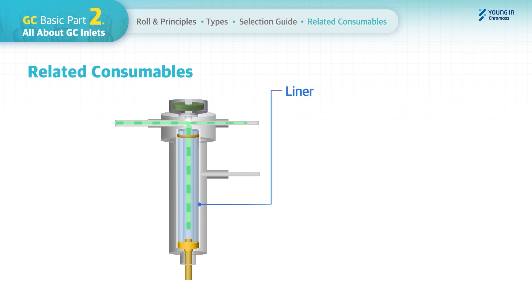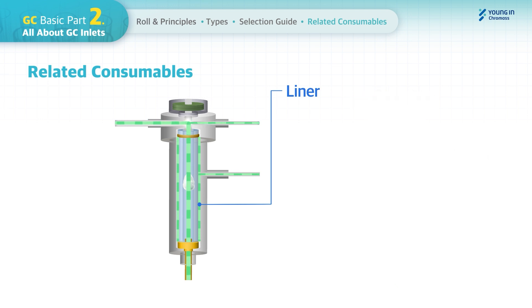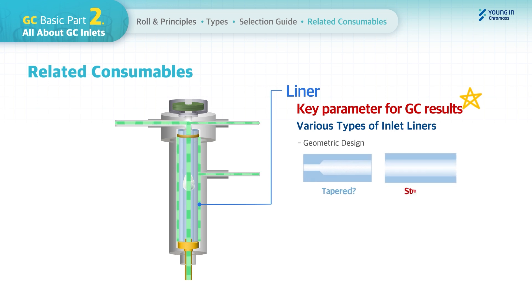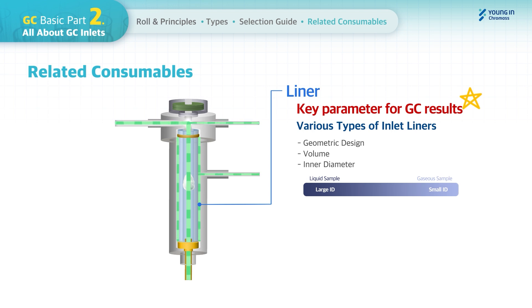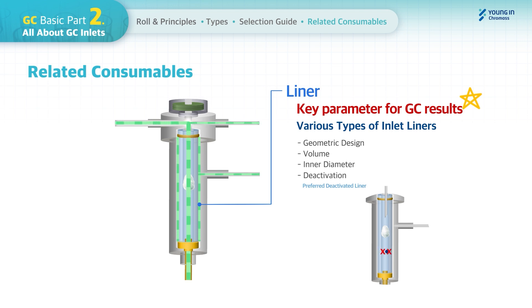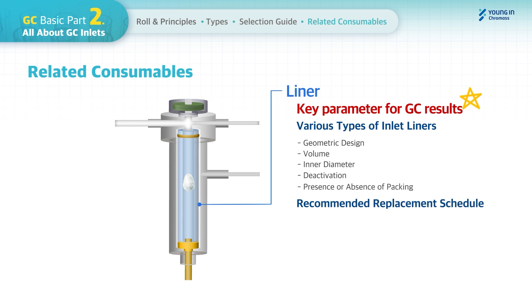A GC inlet liner is located at the entrance of the GC column inside the GC inlet. This is where liquid samples get volatilized and it transfers the injected sample into the GC column while preventing sample residue and non-volatile contaminants from reaching the column. Selecting the right inlet liner directly affects analysis results. There are various types of inlet liners differentiated by geometric design, volume, inner diameter, deactivation, and the presence or absence of packing. The inlet liner should be inspected daily and replaced every month or when any related symptoms occur.